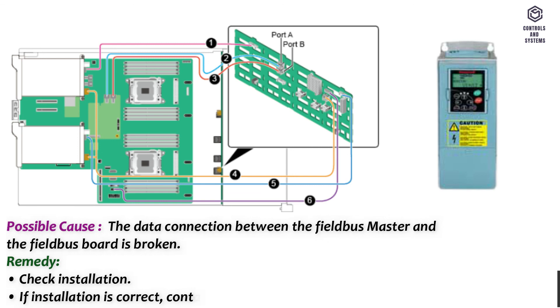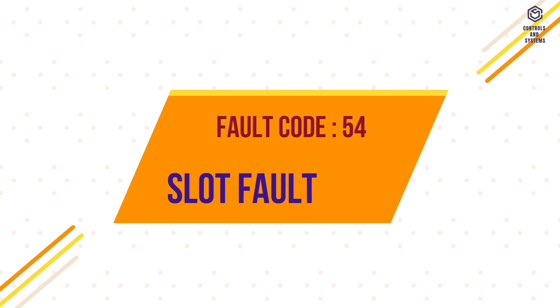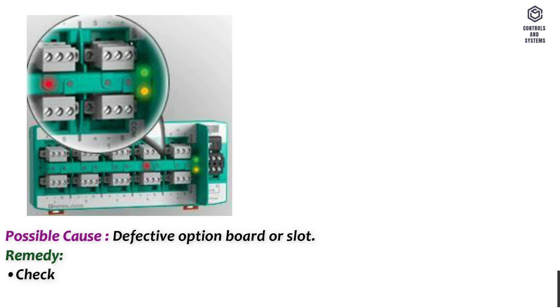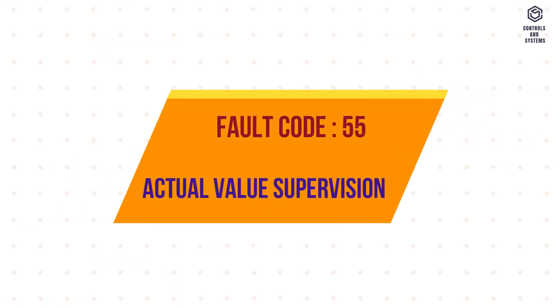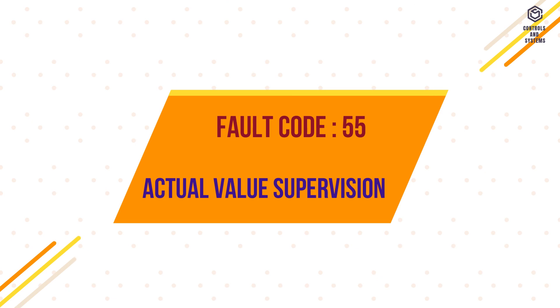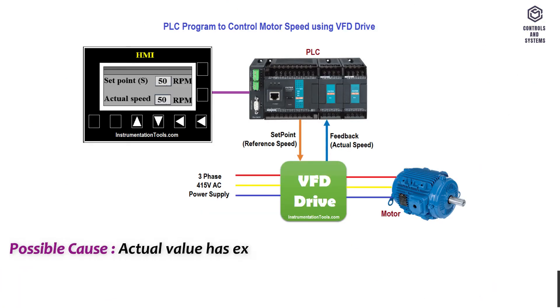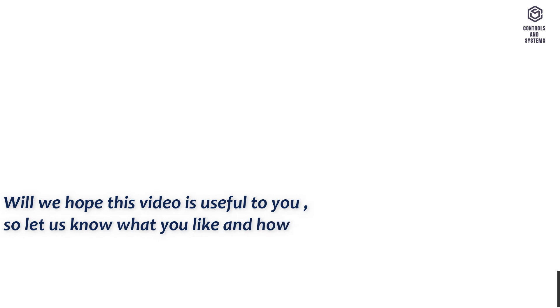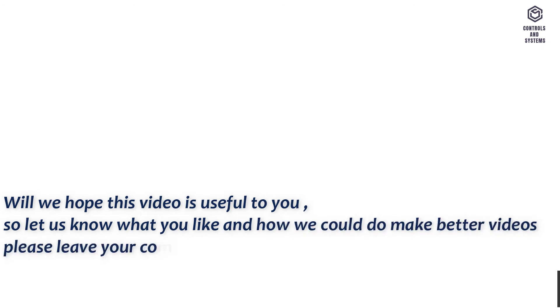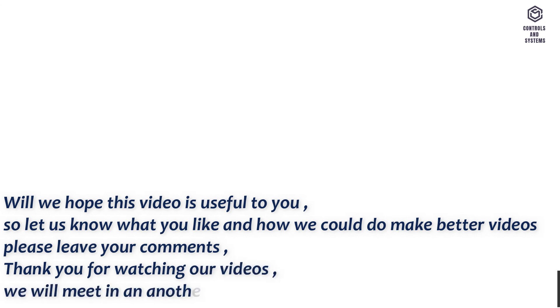Fault code 54 – Slot fault. Possible cause: defective option board or slot. Remedy: check the board and slot; contact technical support. Fault code 55 – Actual value supervision. Possible cause: actual value has exceeded or fallen below the actual value supervision limit. Remedy: check the process. We hope this video is useful to you — please leave your comments. Thank you for watching.